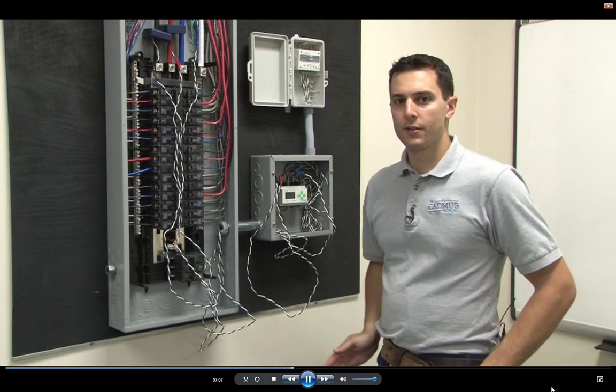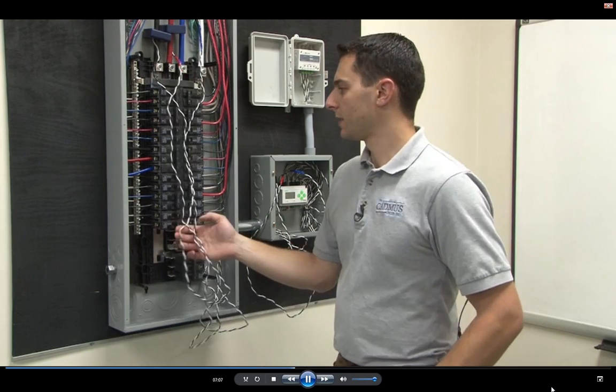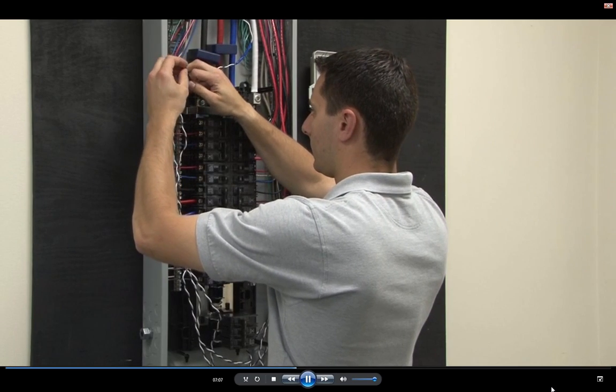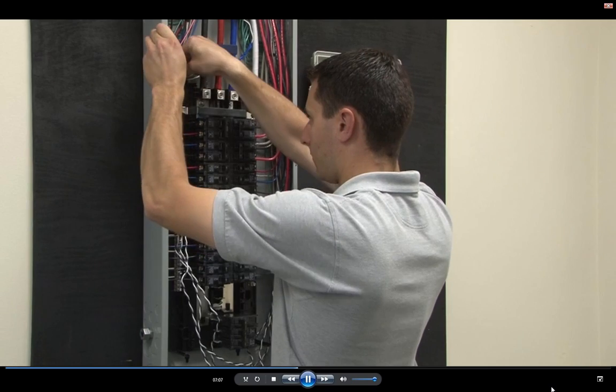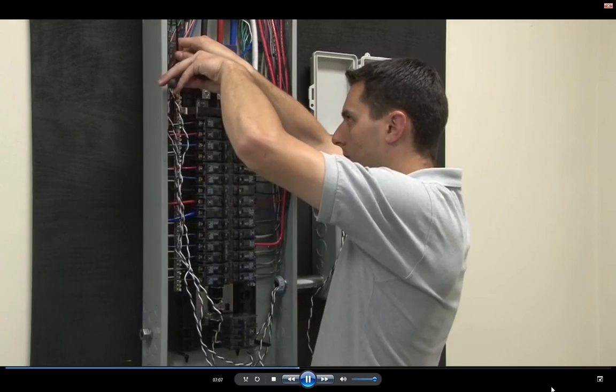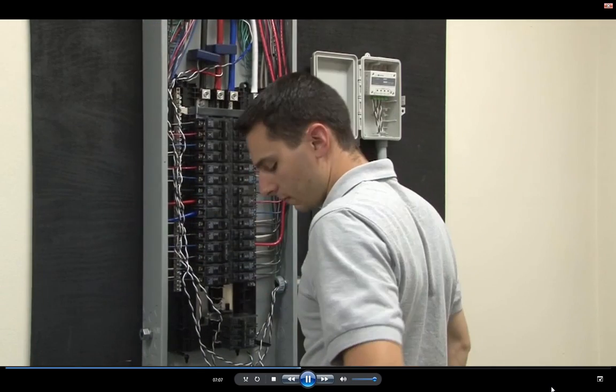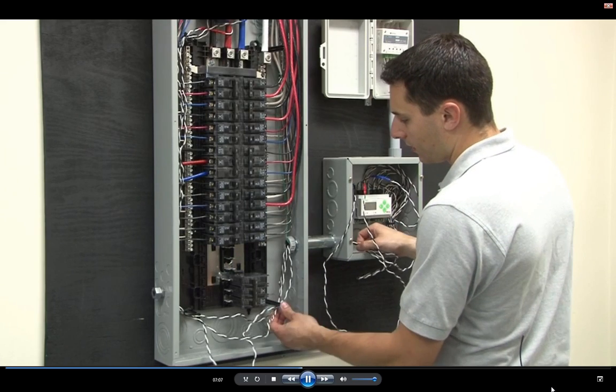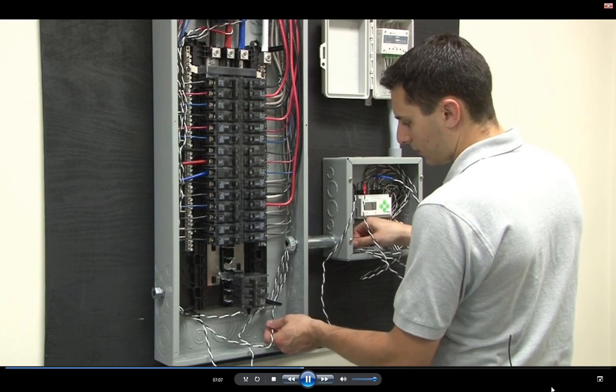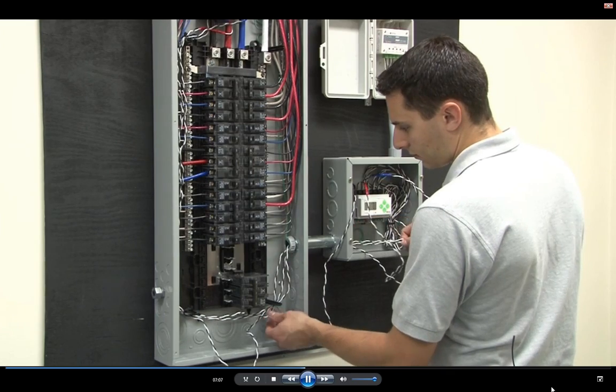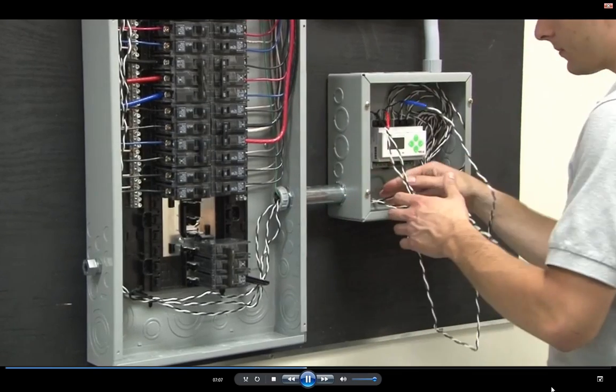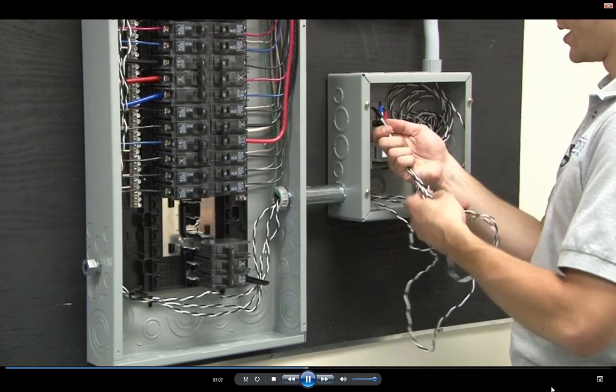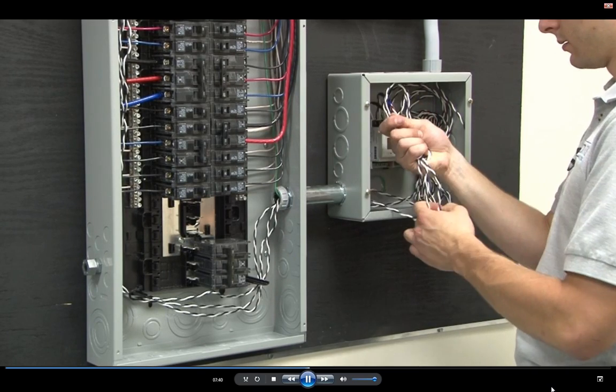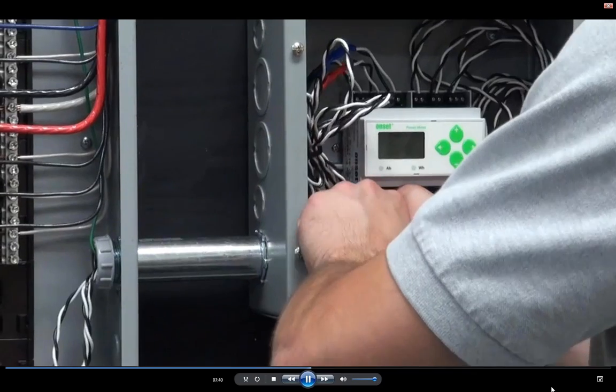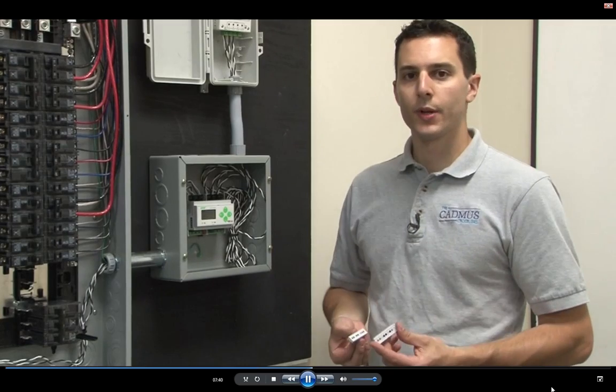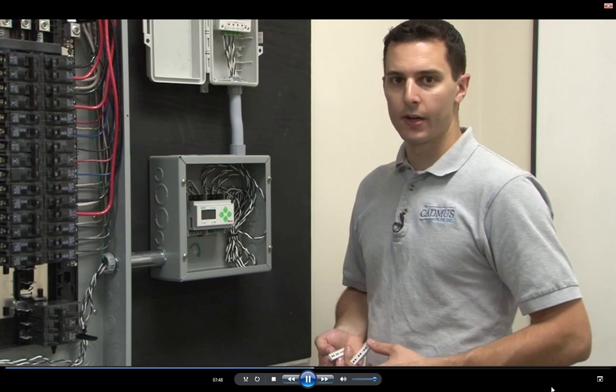Now that all of our CTs are installed, we can organize them with zip ties. Then we'll pull the excess wiring into the enclosure. And once again, we'll organize these conductors with a zip tie as well. We can now put our terminal covers back on the top terminals of our E50B2.